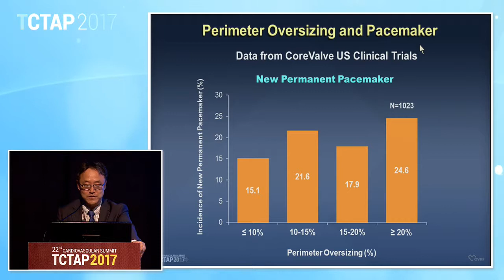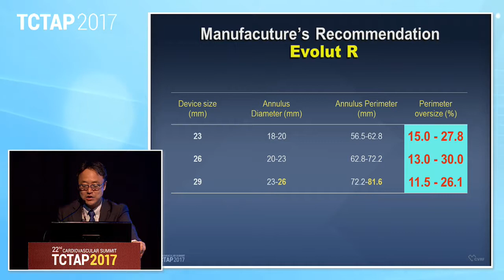Perimeter oversizing, however, is associated with a higher pacemaker insertion rate. Still, with the Evolut R, about 20% usually received a permanent pacemaker. The manufacturer also recommends a larger size, with oversizing of up to 30%. So choose a large one.